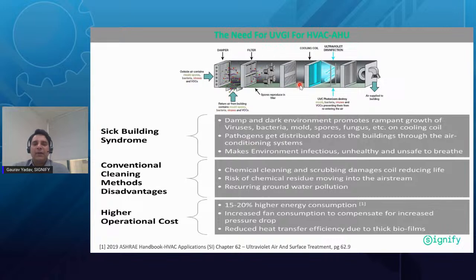All those bacteria and viruses coming with the air get accumulated on the cooling coil. The cooling coil proves to be a breeding ground for them because of the moist and dark environment, which is the best environment for their growth. So they accumulate on the cooling coil, and that is why in most AHUs, after some time, you can see an accumulation of biofilm on the cooling coil.